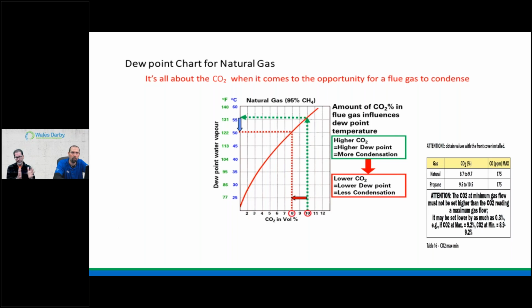So again, to the right, this is one of the manuals that I just grabbed this out of. You have natural gas, you have propane. They're talking about parameters between 8.7 and 9.7, okay? So therefore, you have that range, and here I think it's saying as much as a 0.3 difference between the low fire and high fire. But just understanding what this is all trying to achieve for you is that we want to maximize, as soon as we can, achieving that 130 and less so that we start condensing because of that dew point.